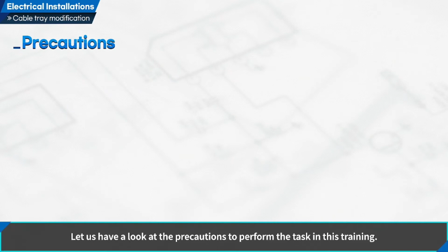First, when cutting the cable tray, confirm the location to be cut. When analyzing the drawings, check how the cable tray will be bent, because the location to be cut varies depending on how it will be bent. Emphasize important or particular points on the drawings with a highlighter.